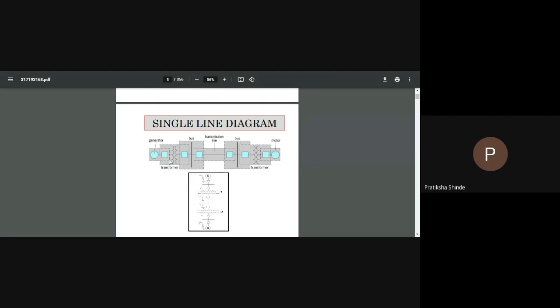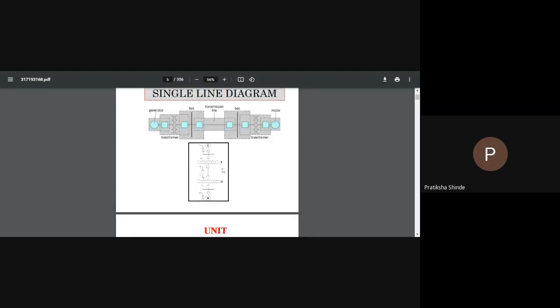It can be denoted with the help of symbols. Suppose the first one is your generator, second is the transformer. The dotted line rectangle shows the combined protection for your transformer and generator. The second rectangular box shows the protection for your transformer - circuit breaker, again circuit breaker, and transformer. So similarly, from generator to motor, this is your single line diagram.